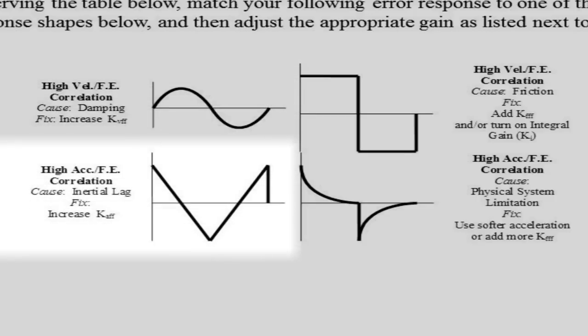The bottom left diagram shows a high correlation between the following error and the commanded acceleration. They have the same shape. This is due to inertial lag. To compensate for this, increase kAFF.